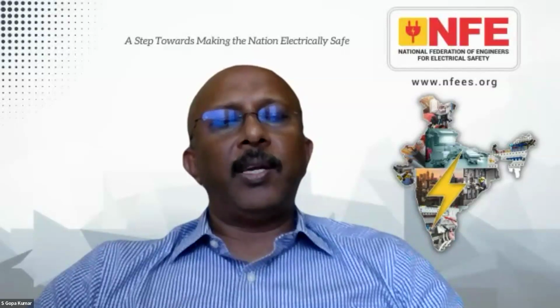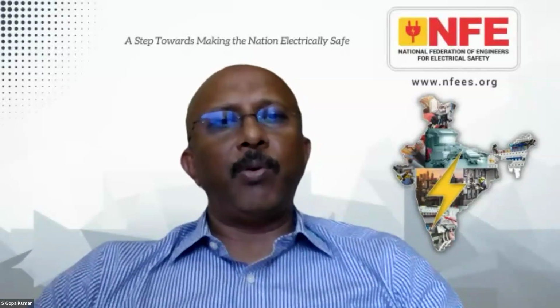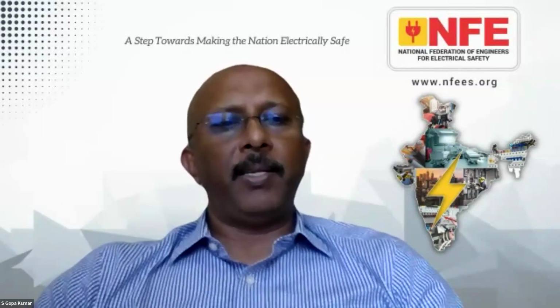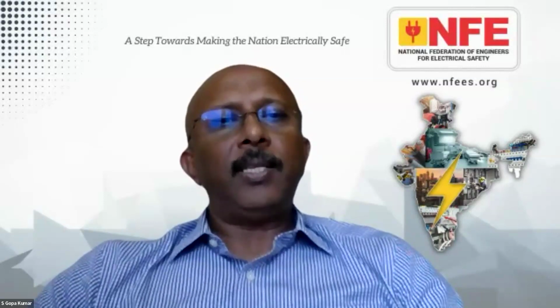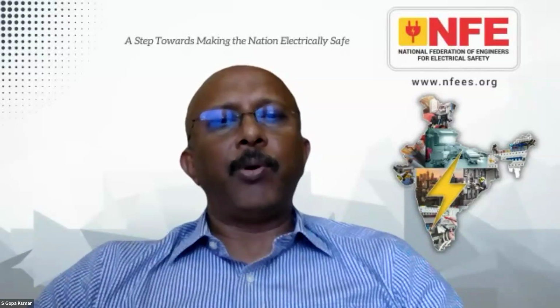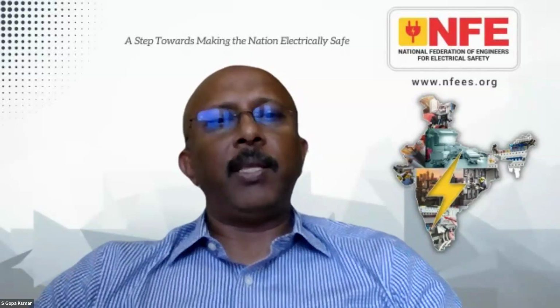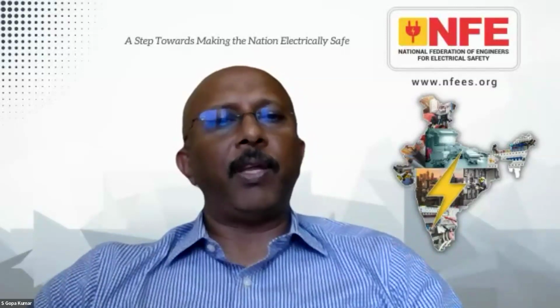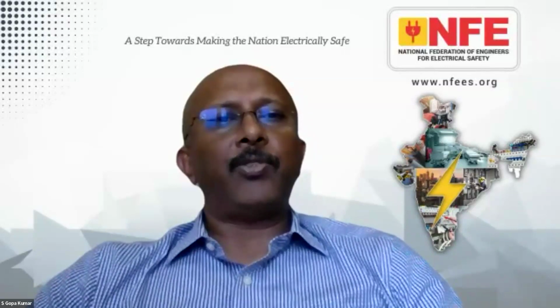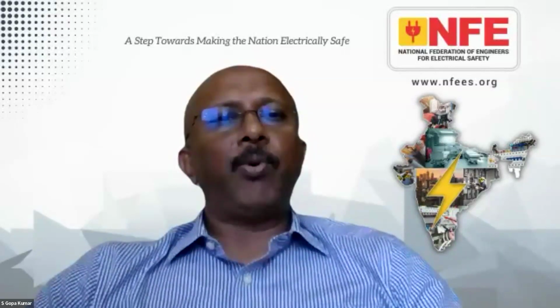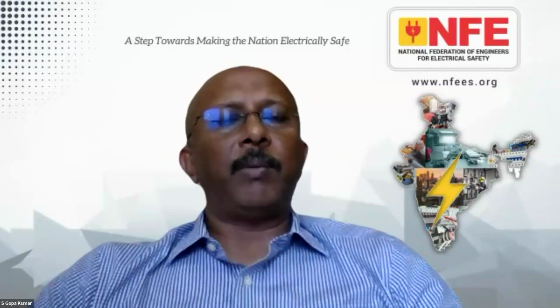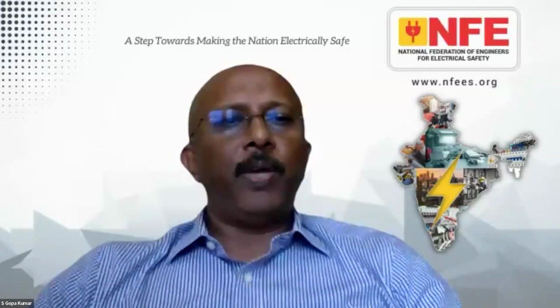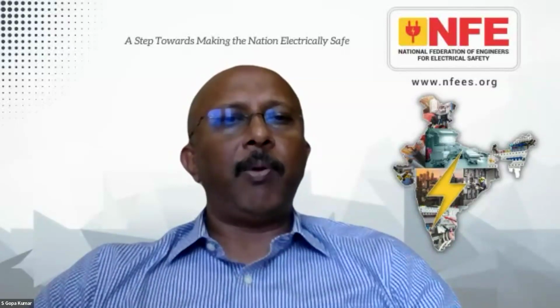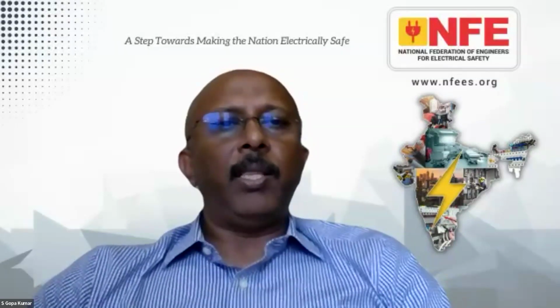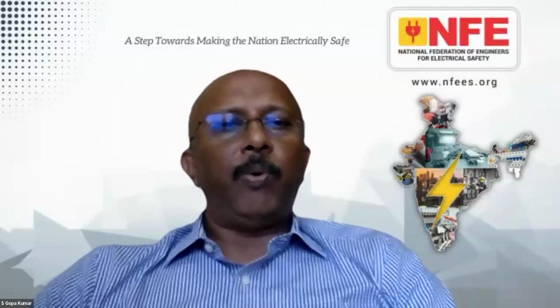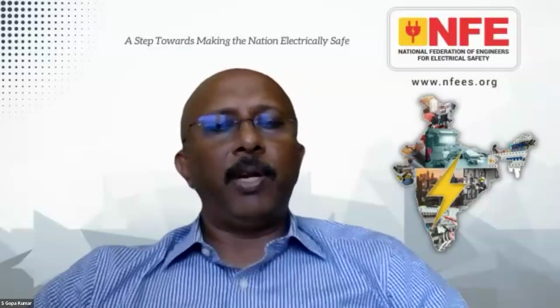I used to do this test in industry. How do I educate my technicians to do it in a larger installation with higher circuit currents? There we first make the arc flash analysis. We have to find out and select the appropriate arc suit. Since this is a live test, you sometimes have to open the bus bars or some of the live parts. So the person has to wear the appropriate PPE, for example the arc flash suit, and then only can you do the test. Don't try to open parts in a live condition and do the test.